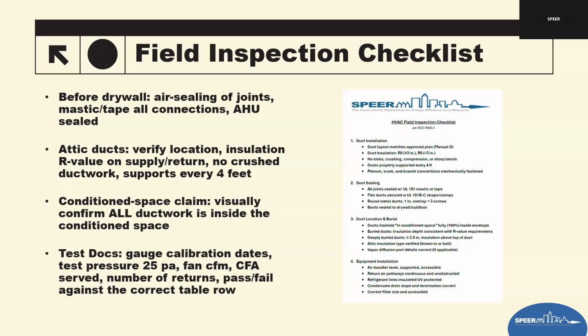There's another question here. Please clarify: if a spray foamed attic is using ERI performance, can I not use R6 ducts? It goes back to, and this is why it was clarified, great question, Dave. If it's a foam encapsulated house, regardless of ERI performance or prescriptive, if they're claiming it's in conditioned space, the ducts don't even really have to be insulated because they're fully inside conditioned space. However, they cannot be in contact with the outermost air barrier. They must be on the conditioned side of the thermal boundary, which is the insulation, to be considered fully in conditioned space. So a lot of builders, for consistency, will buy R8 on every home, regardless of whether it's batted, blown, or foamed.